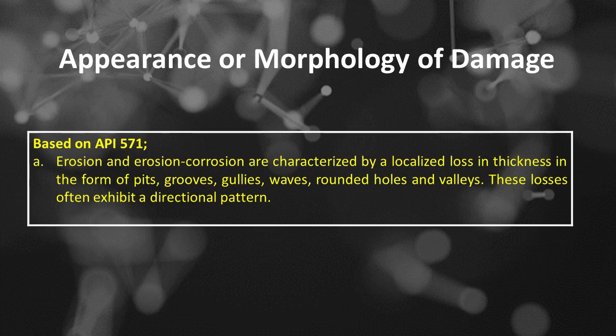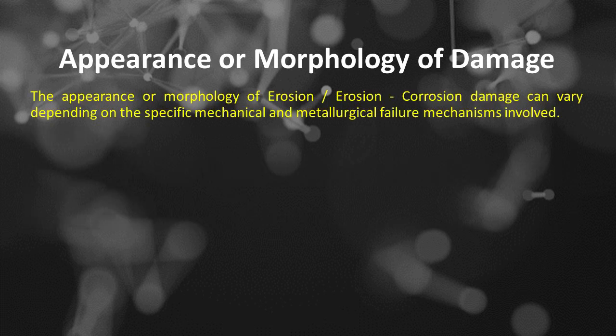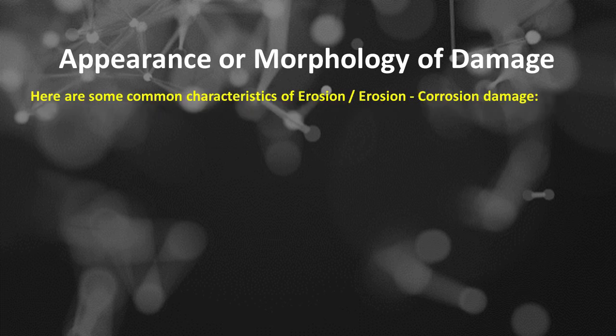The appearance or morphology of erosion and erosion-corrosion damage based on API 571. The first is that erosion and erosion-corrosion are characterized by a localized loss in thickness in the form of pits, grooves, gullies, waves, rounded holes and valleys. These losses often exhibit a directional pattern. The second is that failures can occur in a relatively short time. The appearance of erosion and erosion-corrosion damage can vary depending on the specific mechanical and metallurgical failure mechanisms involved. Here are some common characteristics of erosion and erosion-corrosion damage.